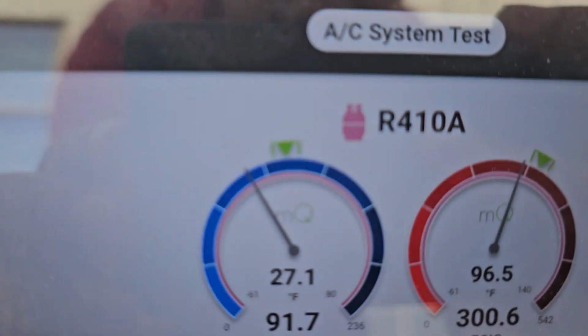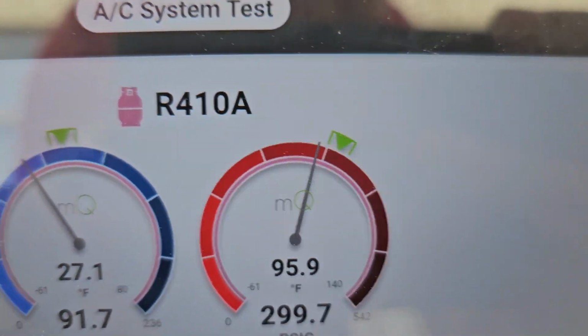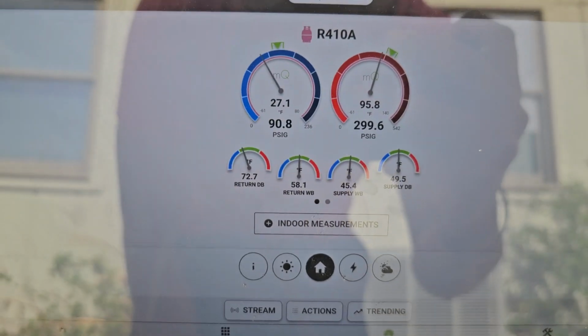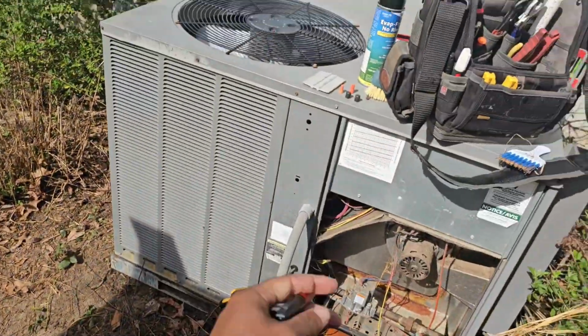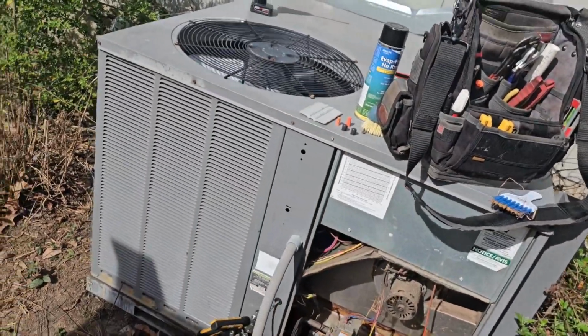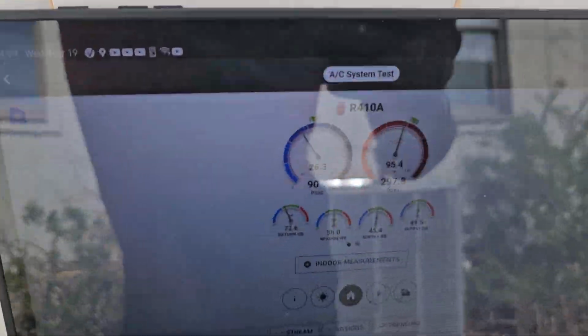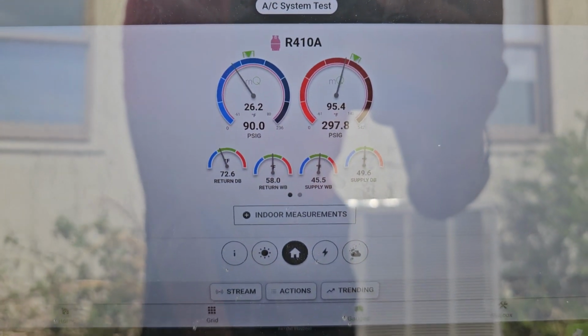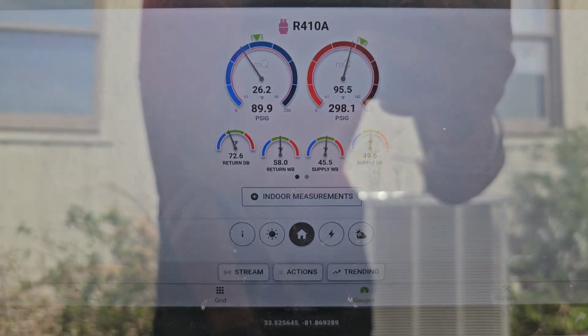Not by much. You can see what Measure Quick would want the pressures to be at, so we're not off by too much, but we're definitely off, and we're probably off within the same margins based on Rheem's manufacturer coil data pressure chart.